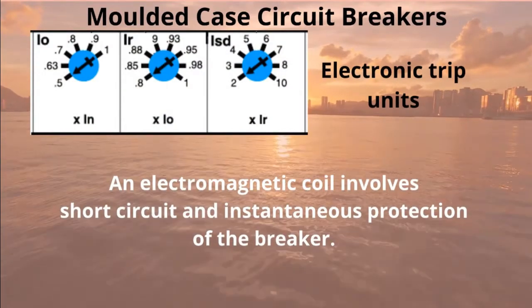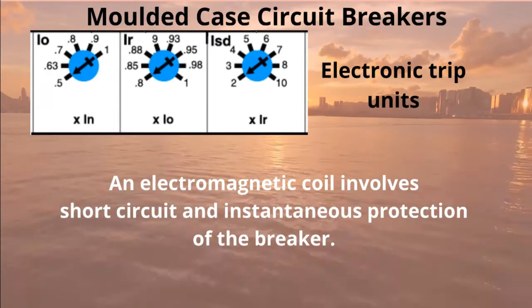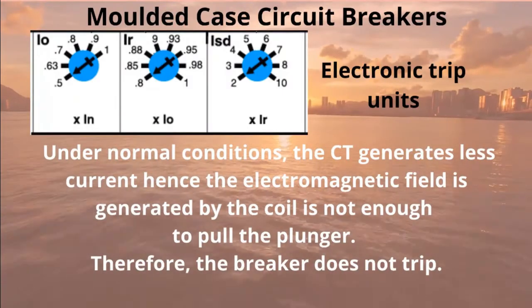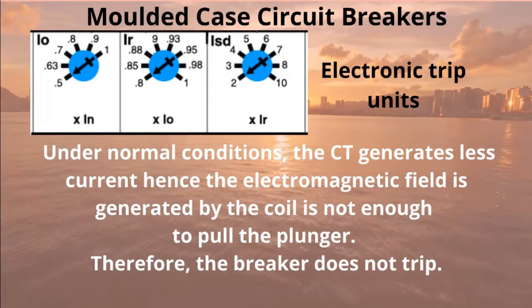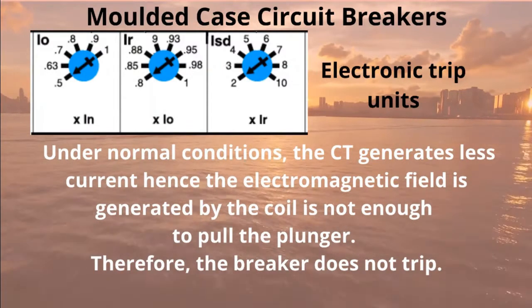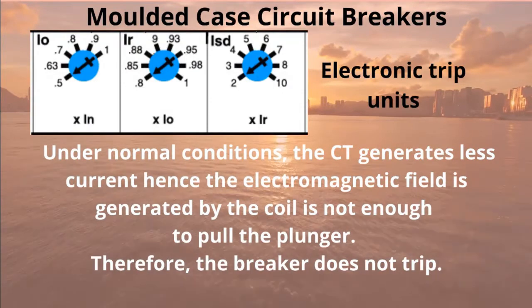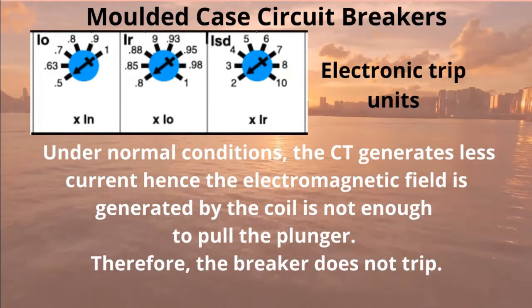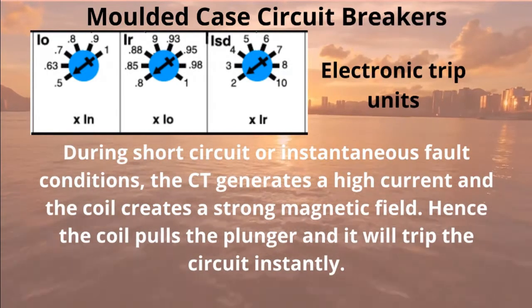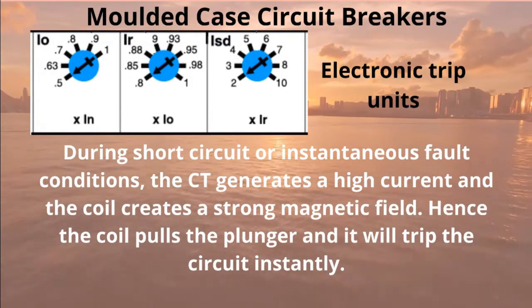For electronic trip units, an electromagnetic coil is involved in short circuit and instantaneous protection of the breaker. Under normal conditions, the CT generates less current, hence the electromagnetic field generated by the coil is not enough to pull the plunger — therefore the breaker does not trip. During short circuit or instantaneous fault conditions, the CT generates a high current and the coil creates a strong magnetic field, hence the coil pulls the plunger and trips the circuit instantly.